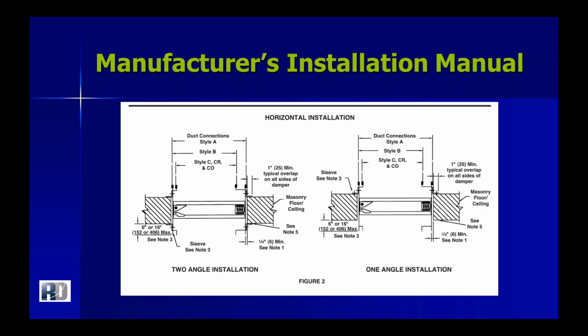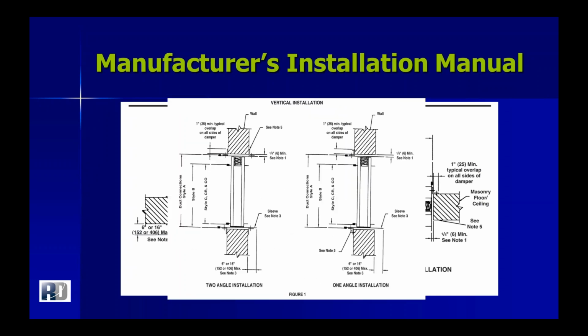Here you can see, and I'm going to breeze on to the next screen because it's pretty much the same thing. This is discussing the retaining angles and how they're supported. So sometimes it's hard to get to both sides of the wall, for example, on a shaft wall. So you can utilize retaining angles on just one side of the wall, and if you do so, you have to screw both into the sleeve and into the wall. And there are different requirements for how far apart the spacing of those screws need to be, whether it's in the wall or the sleeve.